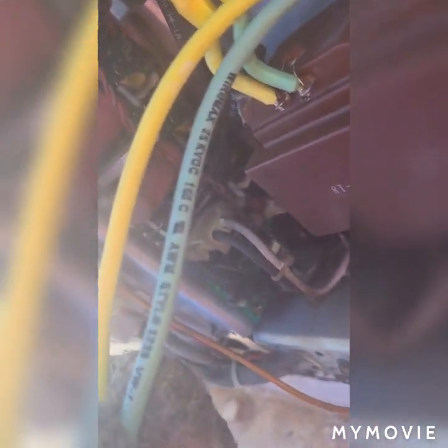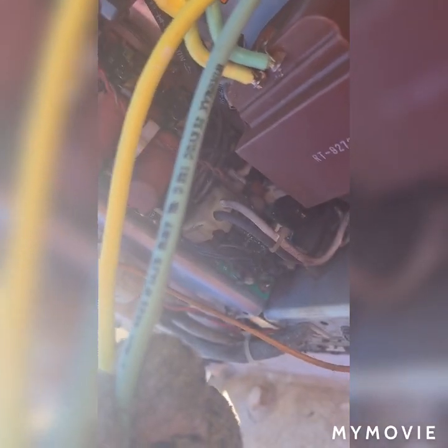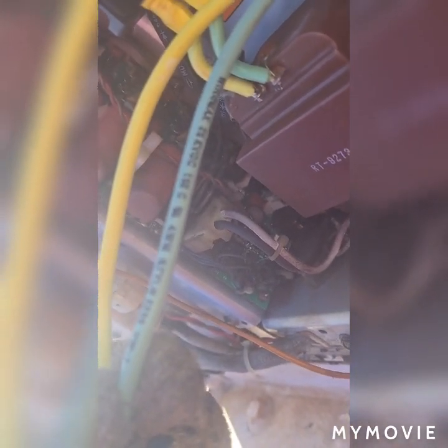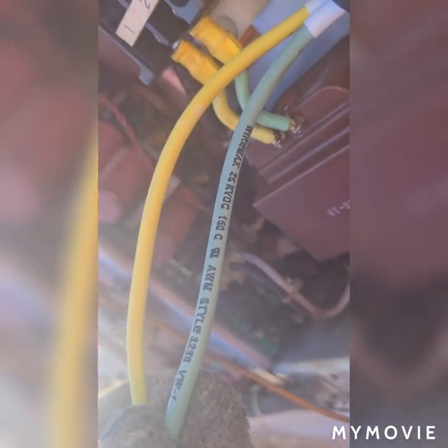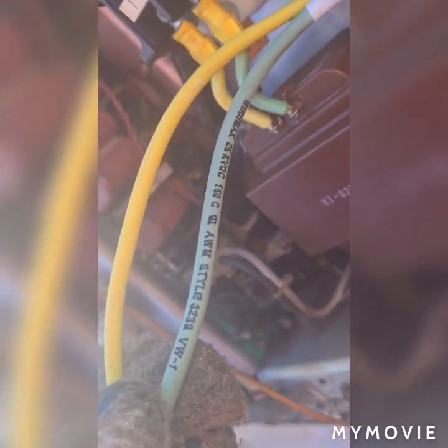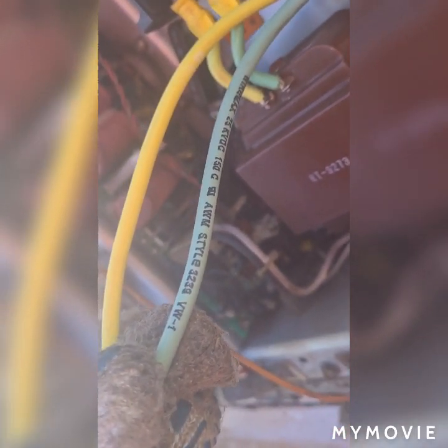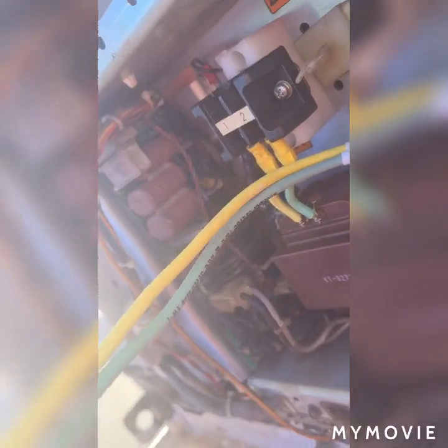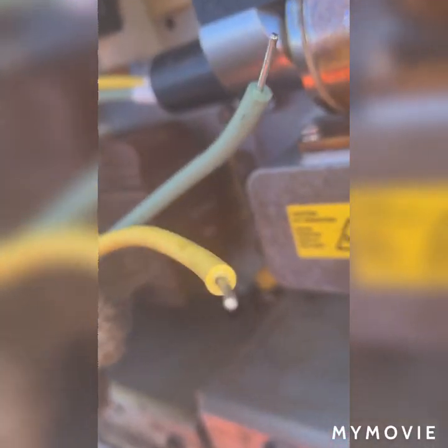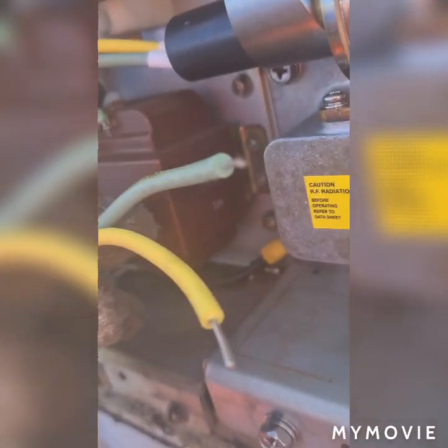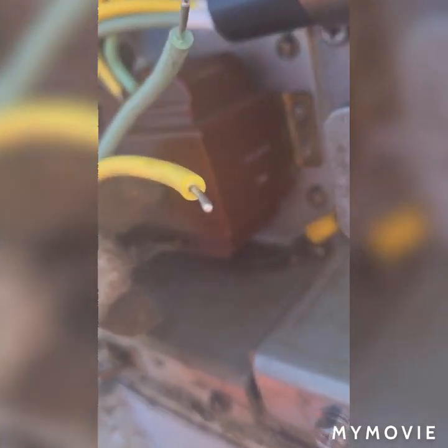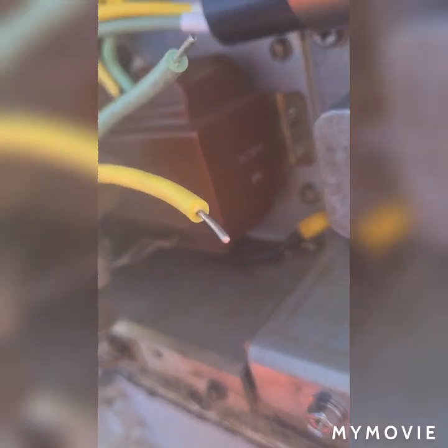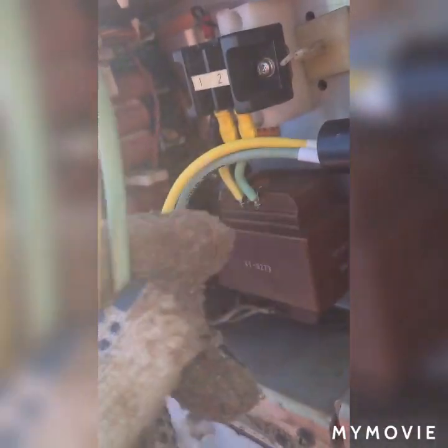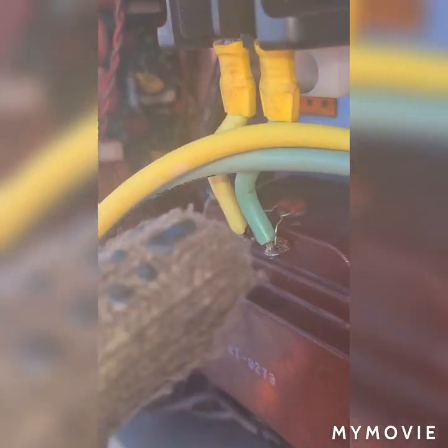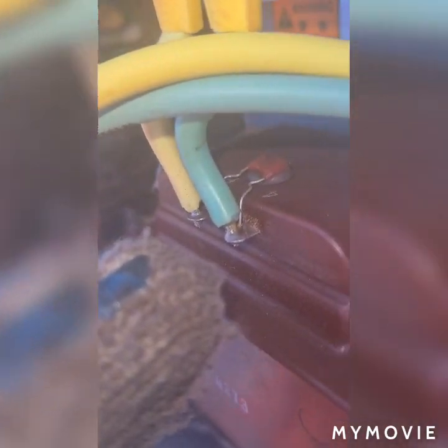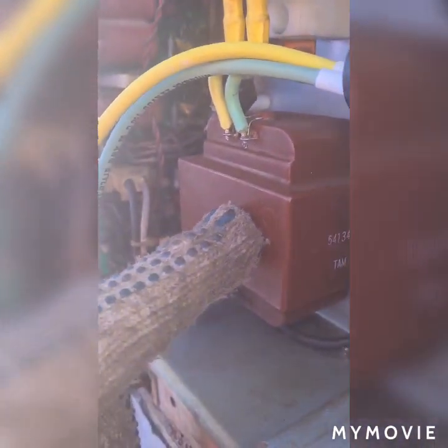This cable, as you can find, is rated for max 25 kilovolts, 150 degrees Celsius. This is the high voltage cable. The insulation is very thick and the conductor size is very thin, because this is the high voltage system of the magnetron. There is a capacitor in parallel with this high voltage transformer.